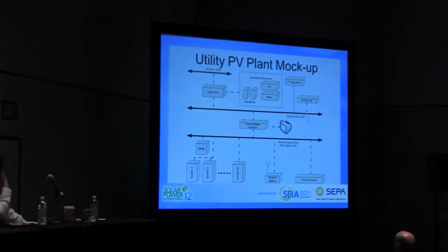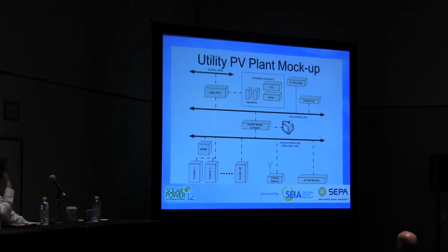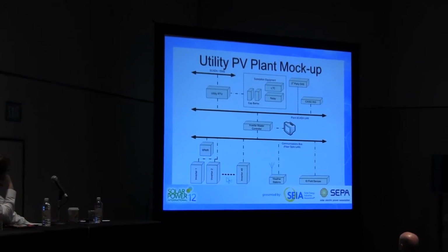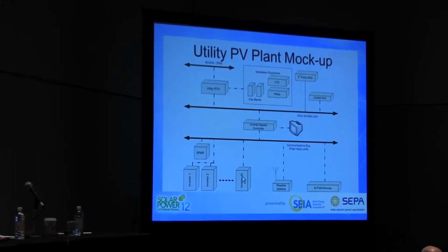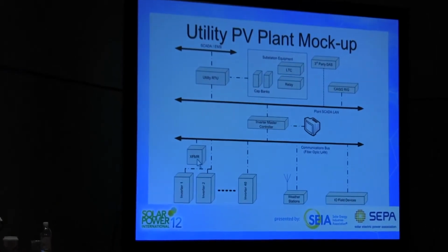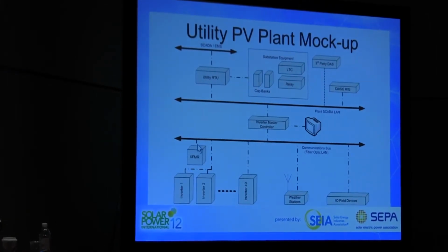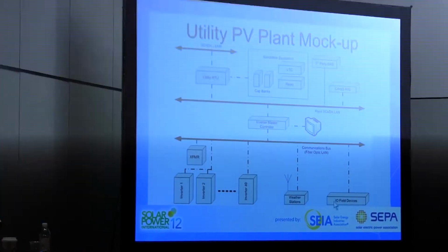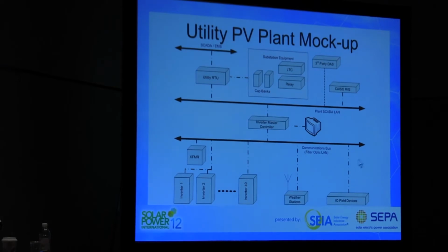So I did this mock-up, and your system may or may not look different, but if we start at the bottom level, there's this inverter master controller. It's controlling a local HMI on the site, fanning out commands to any number of inverters, depending on the plant size. It's pulling data from the transformer, oil temps, that kind of thing. Weather station data is coming in, and then various other I/O field devices.